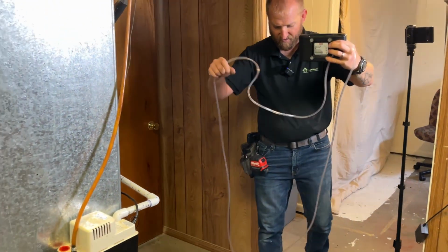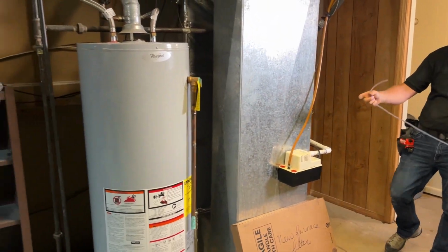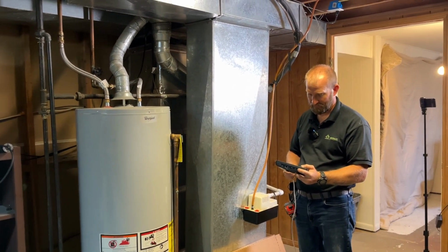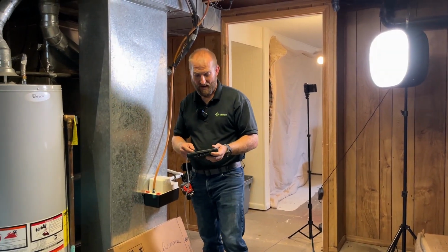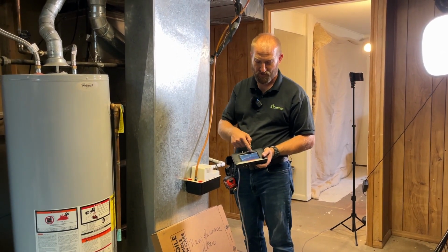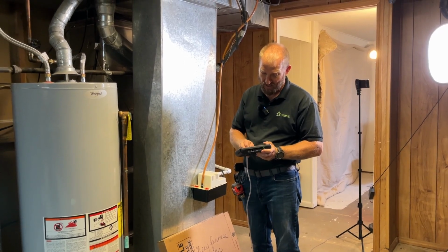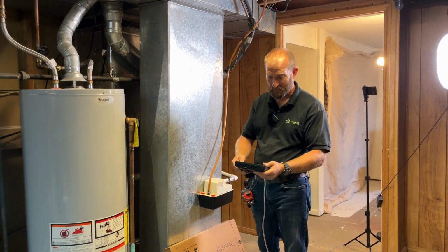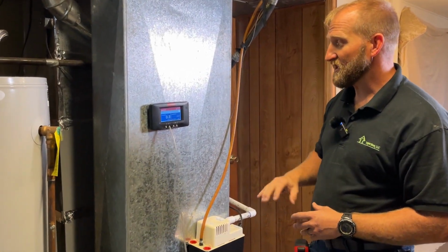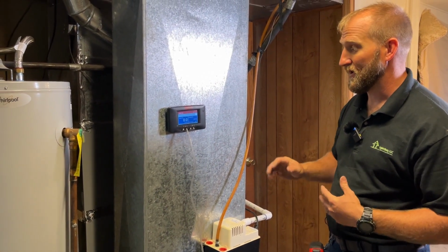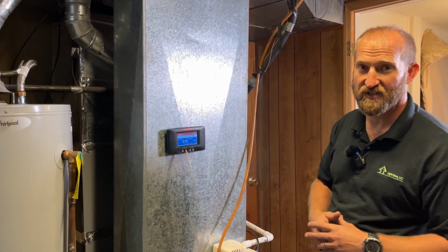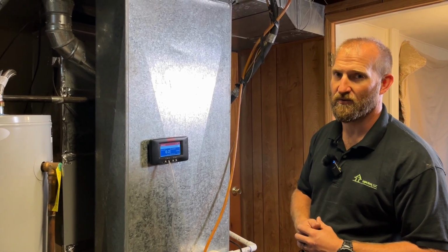We want to measure inside the CAZ here, so we're going to kick this thing back on. It shut off on me. Okay, so once we have our manometer back on, we're going to hook up our reference hose to the outside, so it's referenced to the outside on channel A again. We'll just put that right there. For this, we're just going to log our baseline. We're not going to actually hit the baseline because we want to see what the actual worst depressurization is that the house can go to on its own.